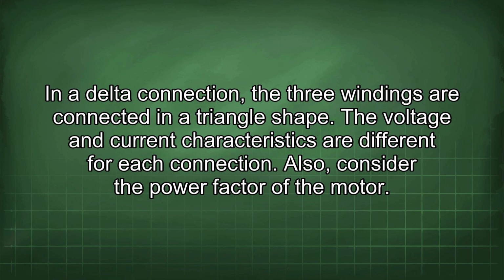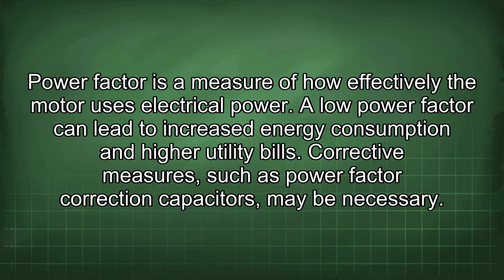Also, consider the power factor of the motor. Power factor is a measure of how effectively the motor uses electrical power. A low power factor can lead to increased energy consumption and higher utility bills. Corrective measures, such as power factor correction capacitors, may be necessary.